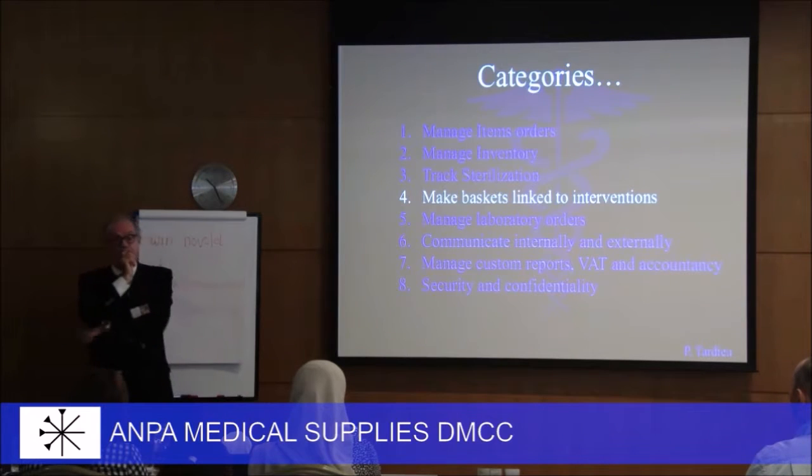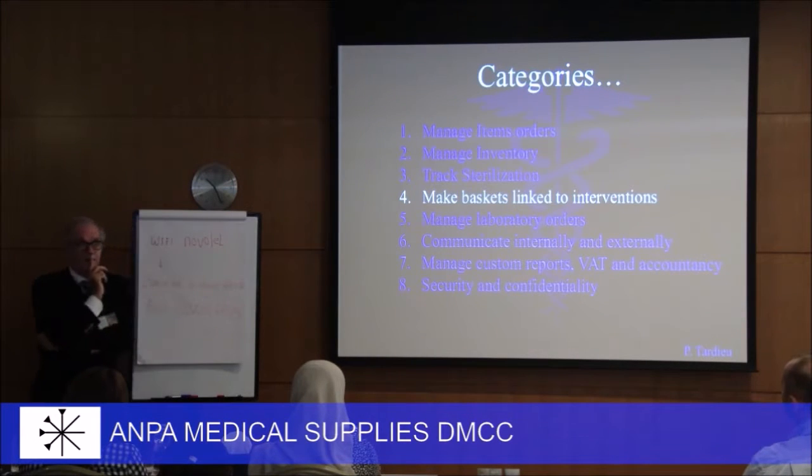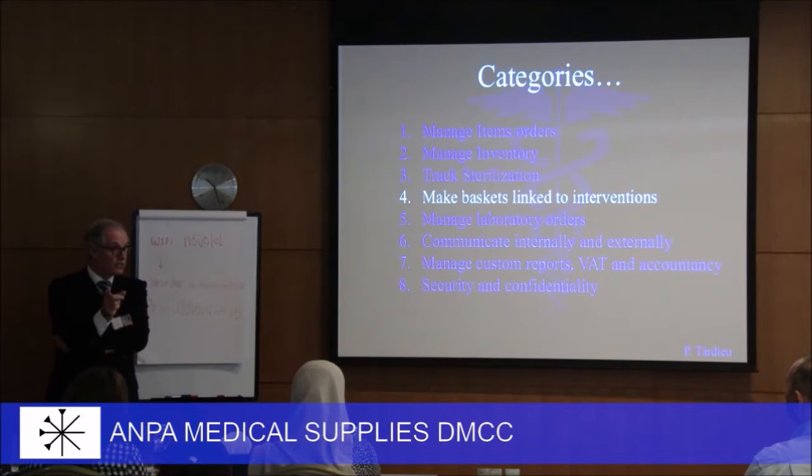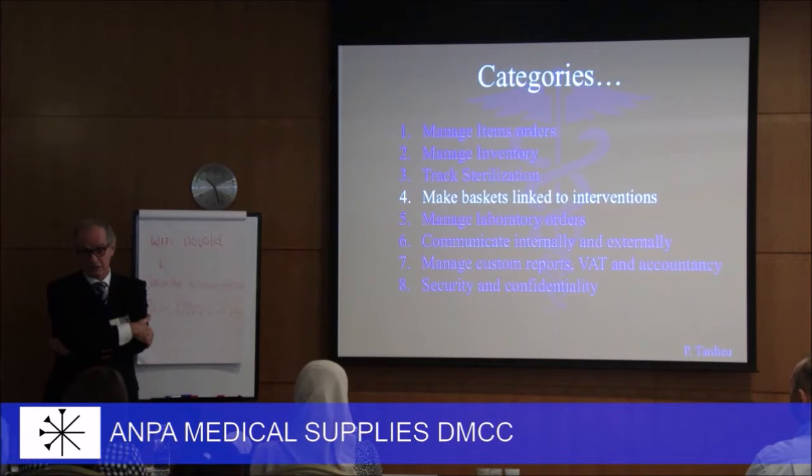The expiry date. In France, I said to you 30 days, 60 days. Here, wrong. We went to a big hospital, I won't say the name, and we asked, do you have an expiry date on your pouches? No. So it doesn't expire? No, it expires in 1 year. 30 days in one country, 1 year in the other country. You have a good chance of not having sterile instruments because of that when you are treated.